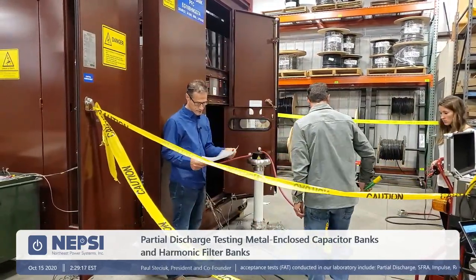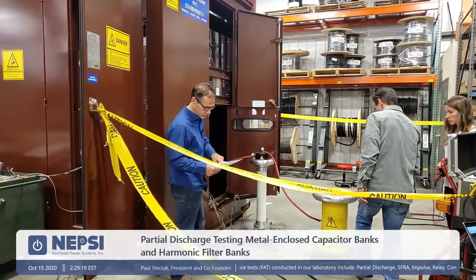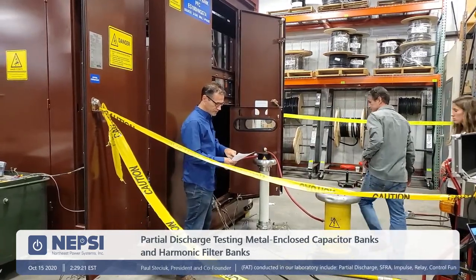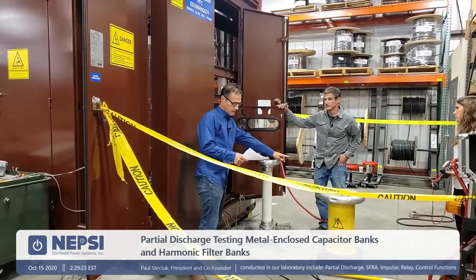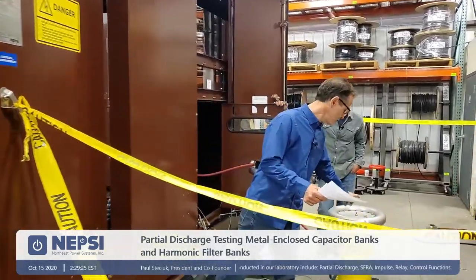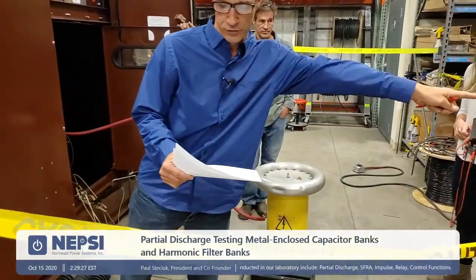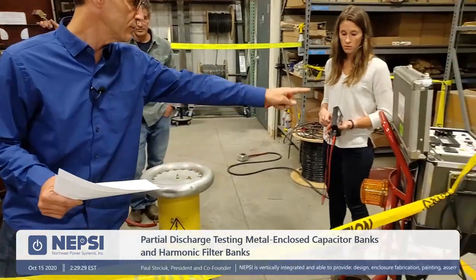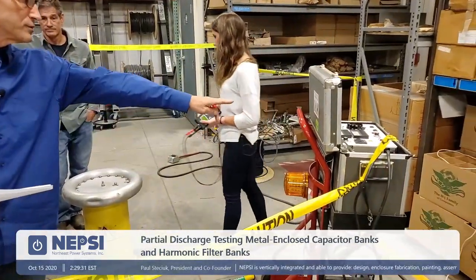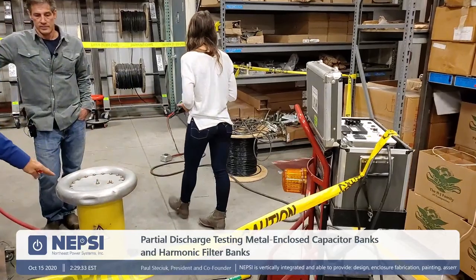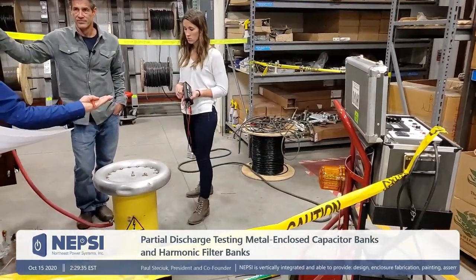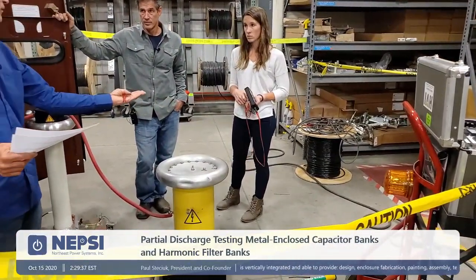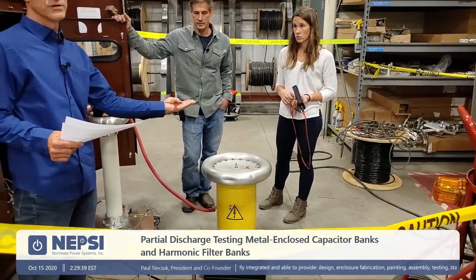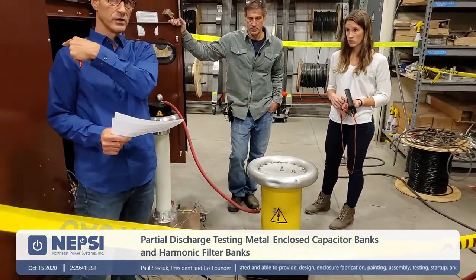Okay, so during the presentation, I will be showing that this is the high voltage source here. So this is the transformer and the high voltage source. These are both calibrated instruments. So this is generating a low voltage signal to the transformer here, which boosts the voltage up. I think the test voltage today is 40 kV, which is 50% of the withstand rating of this device.